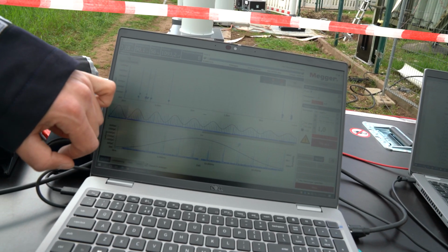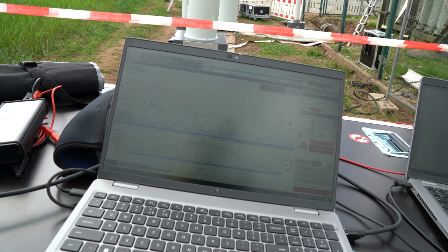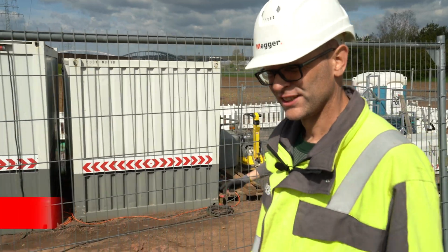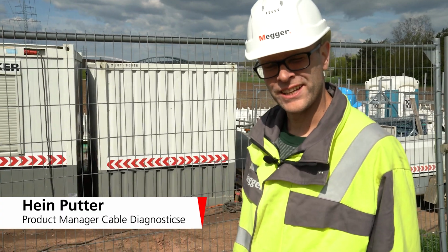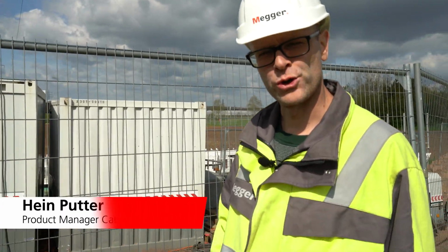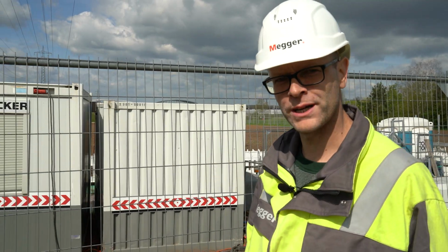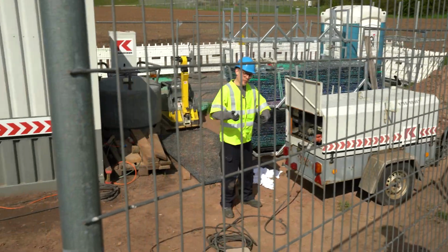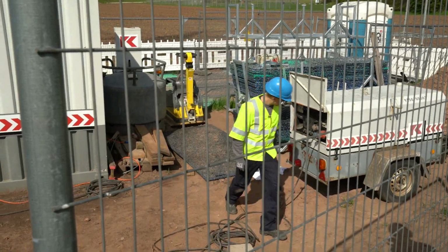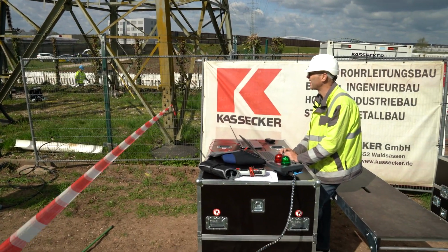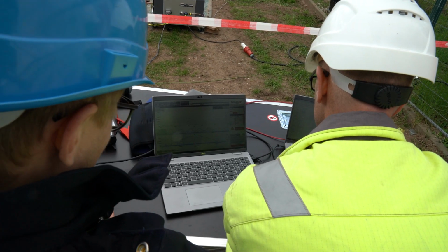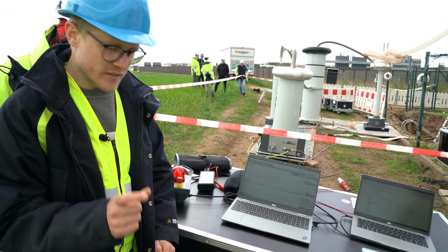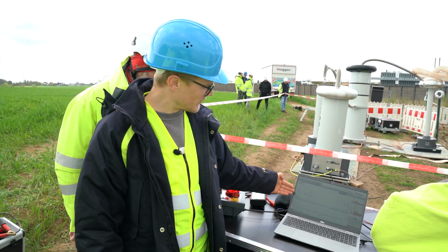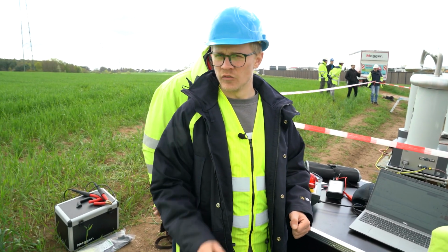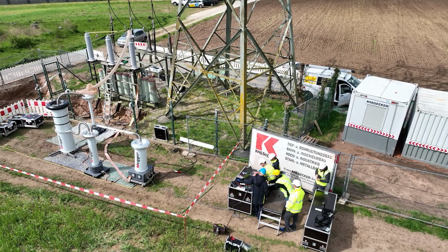What can be seen here during the measurement is asynchronous interference. These are interference pulses that come from our generator, here at the front, and are coupled into the measurement. This is a welding generator, and therefore has no direct earthing. As a result, we have a few higher levels of interference, which makes our measurement somewhat more complicated. Nevertheless, we can carry out the test and localize the partial discharge. The interference signal always comes at equal intervals, regardless of the voltage level of our system. This means that we can effectively calculate and exclude the interference pulses.